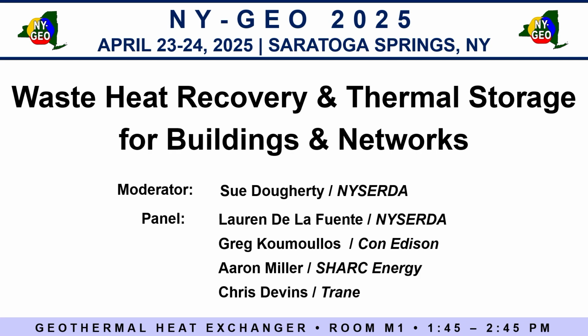Right now we have a project in Vancouver, we have 5 units basically providing enough hot water for 23 million square feet, dealing with massive amounts of sewage. My guys can get all 5 of those machines cleaned in about 6 hours now. So if you design the wastewater holding tank, the battery if you will, and the pumps inside that tank properly, maintenance of the system is really, really simple. You get those tanks and pumps wrong, and not so much. But it's a great question, and we've been doing this now for 15 years, and knock on wood, it's been successful. Thank you.